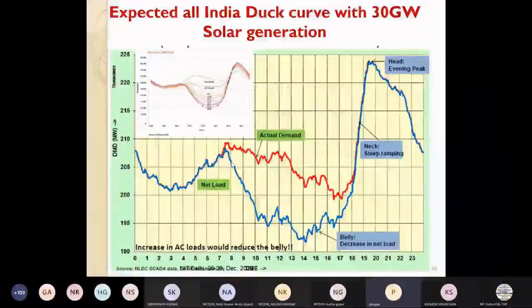So the net load will be the actual demand minus PV generation. PV generation happens from morning 6 o'clock or 8 o'clock to evening 6 o'clock. So because of that, the reverse of that, meaning the negative of that, will cause a reduction in the load. So with higher and higher penetration of solar, what will happen? In spite of the flat load profile, you are getting a downward ramp in the morning time, as well as your evening ramp is increased - it has a longer period of time and a longer ramp also.